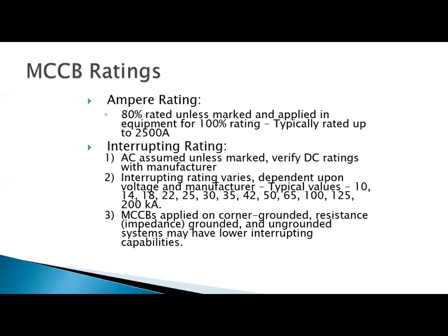We get above 16 amps for a rated amount of time, and it's going to start that process of the bimetallic strip to start to bend. That's fine. Breakers can be rated all the way up to, this says up to 2,500 amps on a molded case breaker. When we get into the different types of breakers, you'll be able to see that we can have breakers all the way up as high as we want, maybe 6,000 amps, but on molded case breakers up to 2,500 amps. And then it comes to interrupting rating. This is extremely important for us to understand. This is true about circuit breakers or fuses.